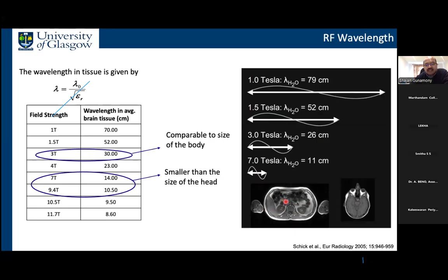So this means at 7 Tesla, the wavelength is about 14 centimeters, which is shorter than the size of the head. So in this photograph here on the right, you can see this pictorially, that at 1 Tesla and 1.5 Tesla, the wavelength is larger than the size of the body. At 7 Tesla, the wavelength is smaller than the size of the head. So if you try to image the human body in a 7 Tesla scanner, you will have multiple of these wavelengths in the body across this imaging slice. That means you have multiple signal maxima and minima within the imaging slice, so you will end up with a really inhomogeneous image. So that's really the fundamental physics problem at higher field strength.